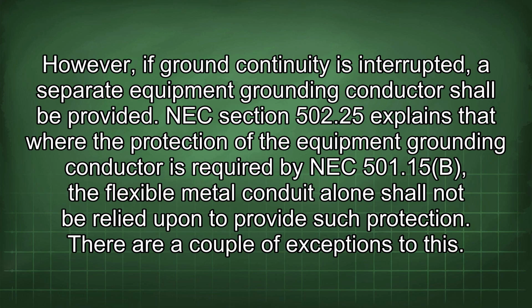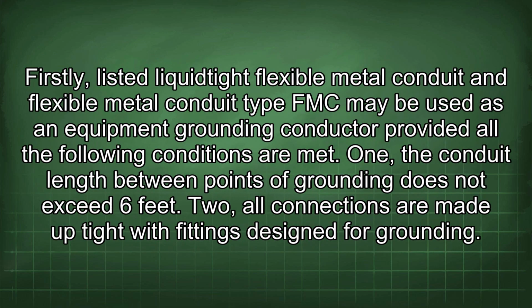NEC Section 502.25 explains that where the protection of the equipment grounding conductor is required by NEC 501.15(B), the flexible metal conduit alone shall not be relied upon to provide such protection. There are a couple of exceptions to this. Firstly, listed liquid-tight flexible metal conduit and flexible metal conduit type FMC may be used as an equipment grounding conductor provided all the following conditions are met.